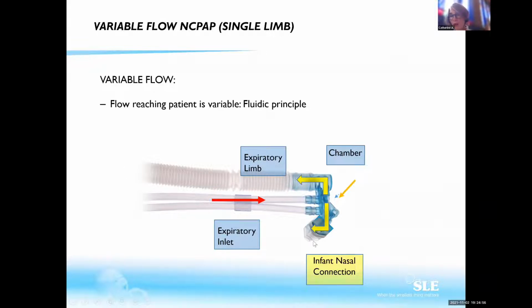But now, whenever a patient takes a breath, by starting a spontaneous breath he will generate a negative pressure. So now the pressure is less important here than here. So automatically you will have more gas diverted to your patient. And that is what is happening here. It means that now you might have 60% of the gas going to your patient and only 40% going to the exhalation.